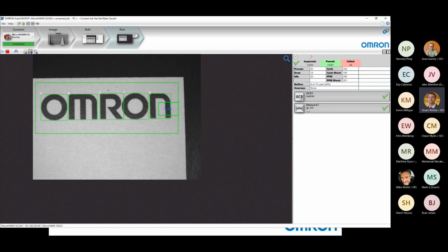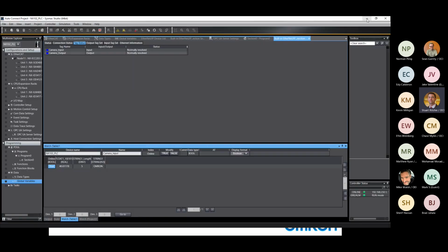My measurement tool is giving me a value of roughly 40. Now in that structure, I look at the contents, and in the first string I have Omron, and in my first floating point register, I'm getting about 40. So if I were using a big array of data for this instead of a structure, I would be looking at 320 bytes of data that you need to find the index that you want, pick it out, parse it, convert it, whatever you need to do. So structures are always very useful in Ethernet IP. And if it's an Omron device, talk to your AE. He's probably got a structure for you.